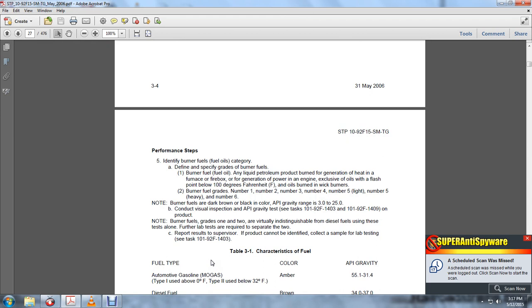Identify burner fuels and fuel oil categories. Define the specialty grades of the burner fuel. Burner fuel: any liquid petroleum product burned for the generation of heat in furnaces or fireboxes, or for the generation of power in an engine, exclusive of the oils with a flash point below 100 degrees Fahrenheit and oils burned in wick burners. Burner fuel grades are number 1, 2, 3, 4, 5 light, 5 heavy, and number 6. Burner fuels are dark brown to black in color, with API gravity ranging from 3.0 to 25.0.